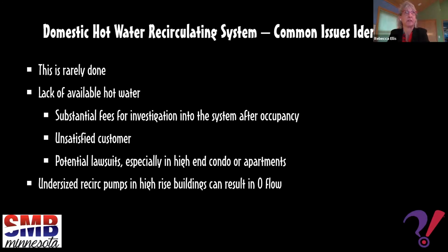It will simply just stop, and there'll be no flow anywhere. And then Mark alluded to these thermal balancing valves. They're balancing valves in the position shown in Miles' schematic, and they're pretty much just 2-position valves. If the water temperature entering the valves is above a certain level, hot enough, they will actually close because they're sensing there's hot water in that riser or in that pipe.